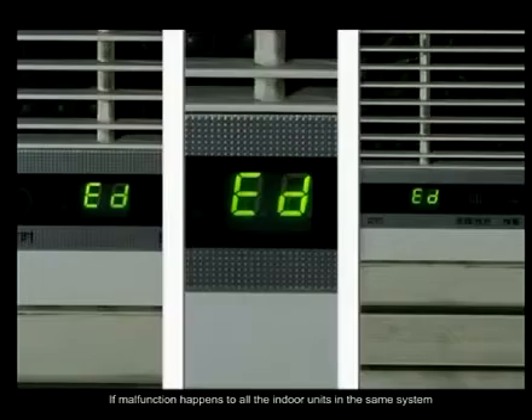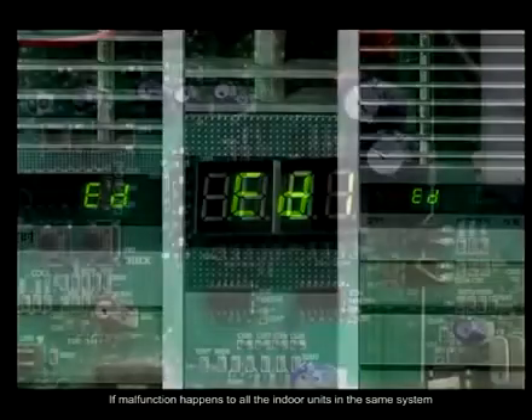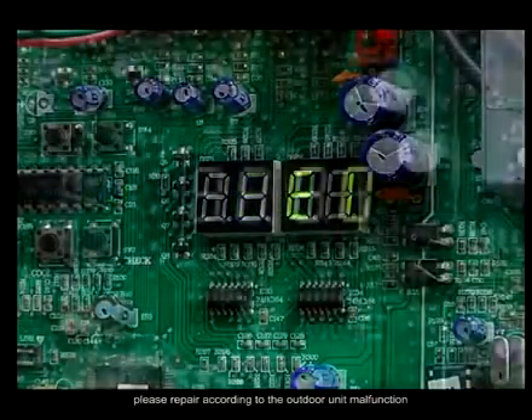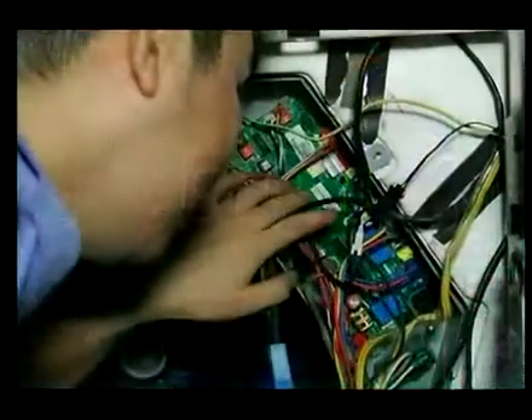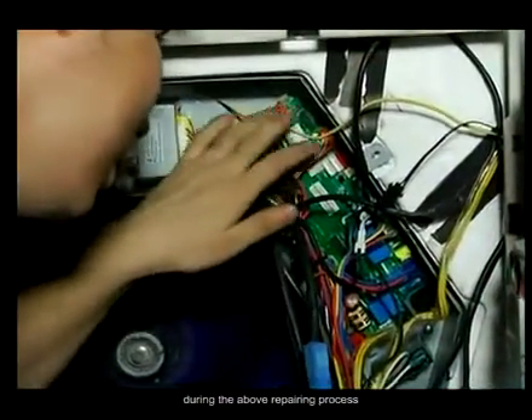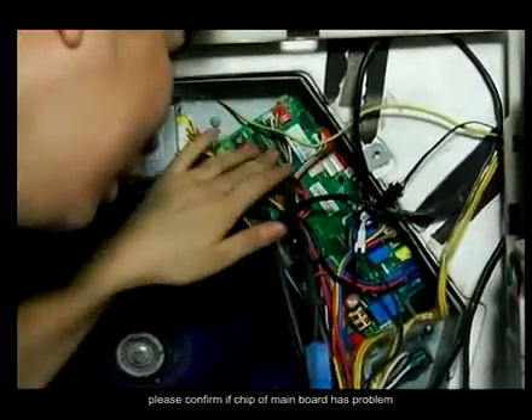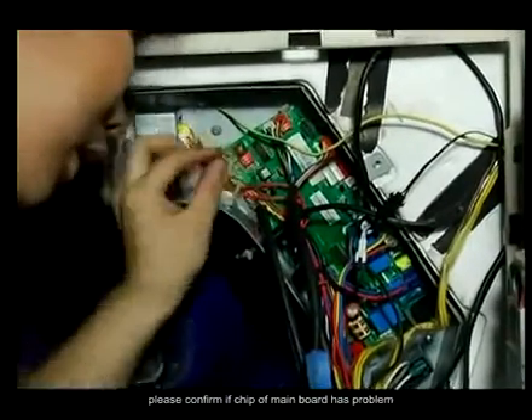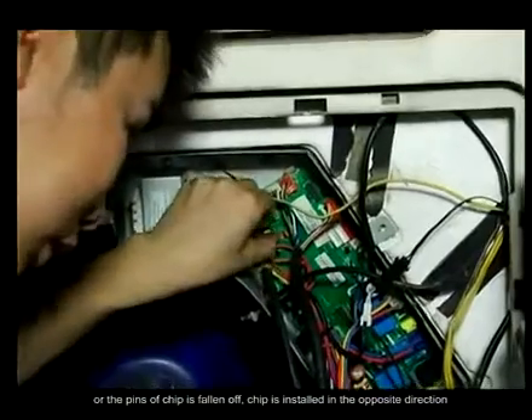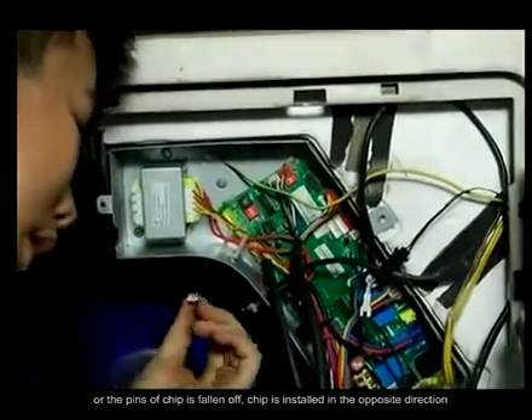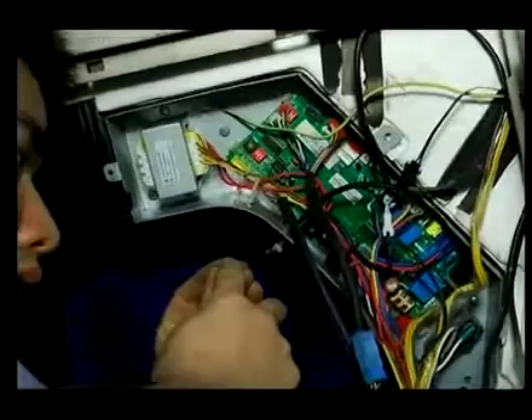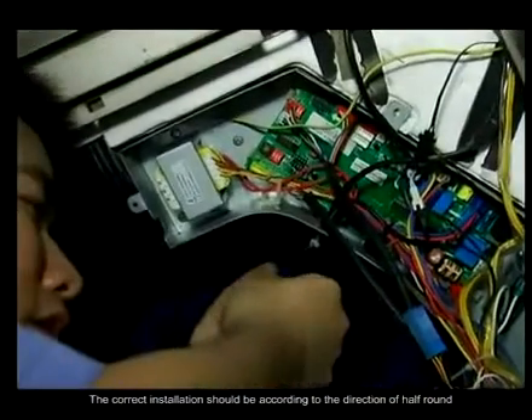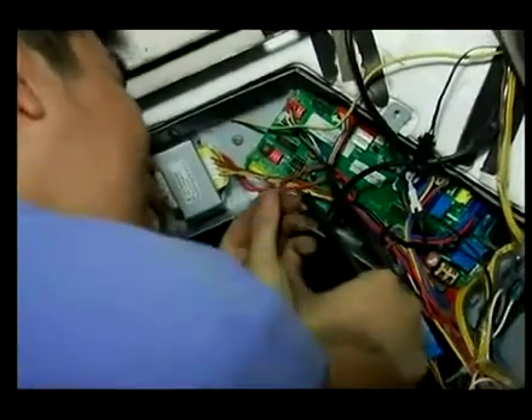If malfunction happens to all the indoor units in the same system, please repair according to the outdoor unit malfunction. During the above repairing process, before changing the indoor main board, please confirm if the chip of the main board has a problem, or the pins of the chip have fallen off. Or the chip is installed in the opposite direction. The correct installation should be according to the direction of the half round.